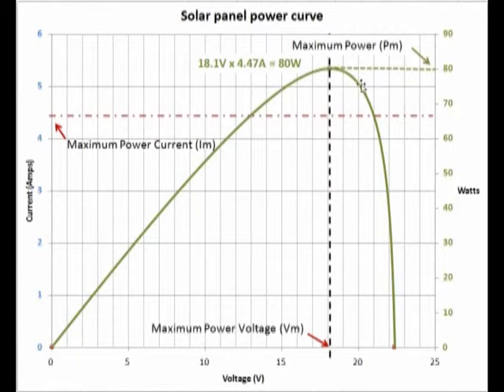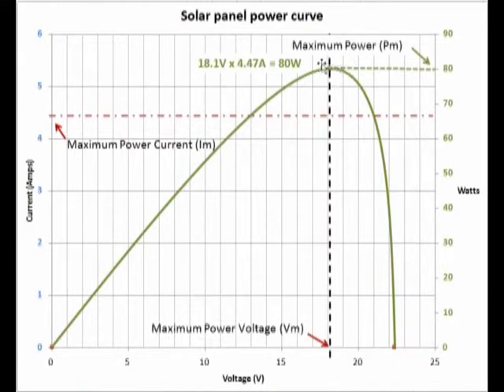So you'll end up with a power curve for this particular solar panel that shows the power going up as voltage and current go up, reaching a peak and then tailing off. This maximum power point is what most charge controllers as well as grid-tie inverters try to achieve on the panel based on sun conditions. Obviously this is the ideal sun condition and you won't get this every single day, but under standardized conditions this is the kind of power curve that would be presented and repeatable.